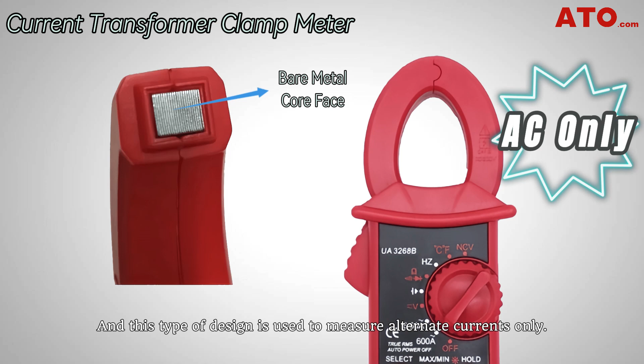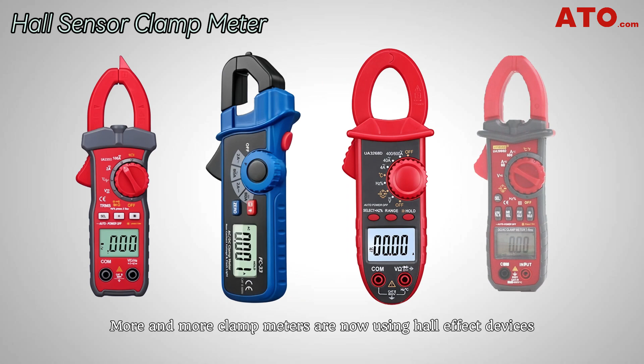Instead, there is no magnetic core placed under the plastic lid of a clamp meter with a Hall sensor. The advantage of this design is that the Hall sensor can detect both alternating and direct currents. More and more clamp meters are now using Hall effect devices to measure both AC and DC current.